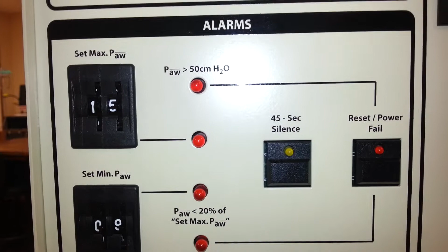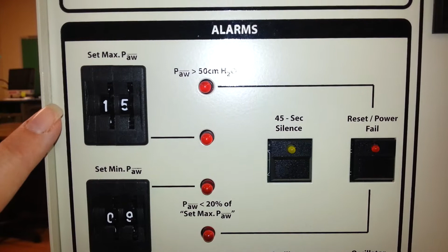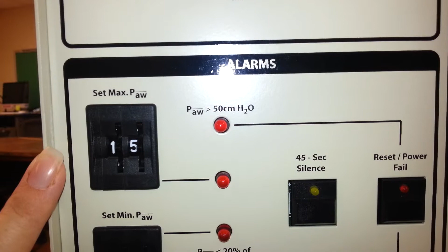Below the mean airway pressure monitor, you see the alarms of this ventilator. See the maximum airway pressure alarm limit and the minimum airway pressure alarm limit. These are set 3 centimeters of water above and below our ordered mean airway pressure of 12.5.